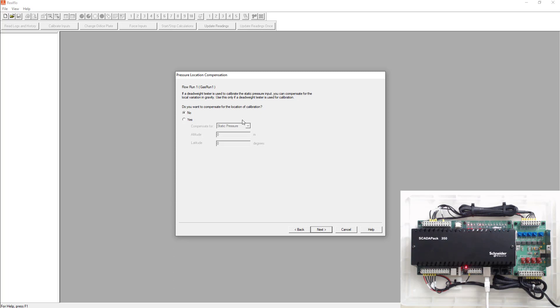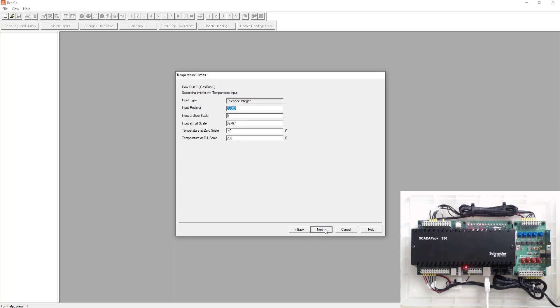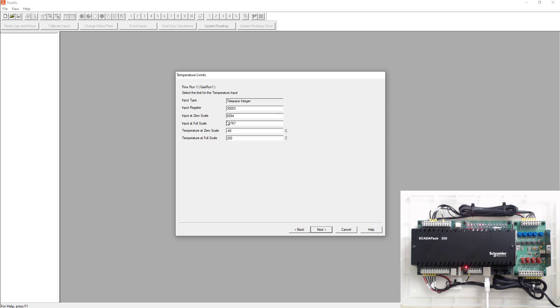Next is going to ask you if you want to only use a deadweight tester used for calibration. We're just going to select no on this. Next is going to ask you for my temperature input. We know that analog input 0, which is 300001 is used, 300002 is being used. So we're going to use 300003. We know that this one's 6554 to 32767. Again, we're going to pretend the scaling for that 4 to 20 milliamp temperature transmitter is negative 40 to 200.